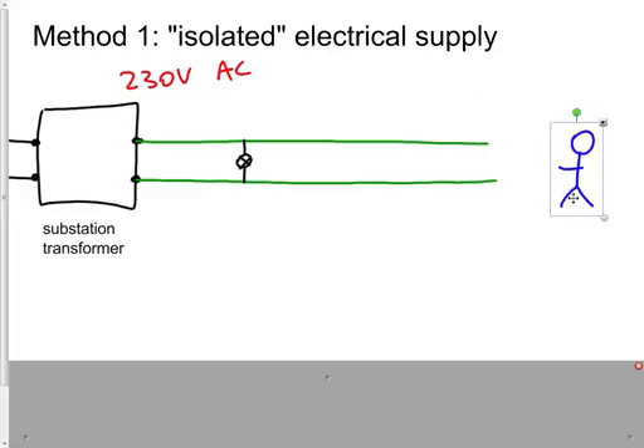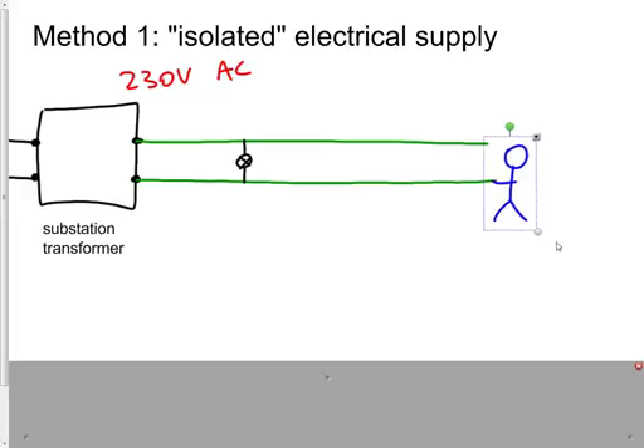But the interesting thing about this is that nothing is connected to the earth. So if you touch one wire and you are also connected to the earth because you're standing on it, that's totally fine in this isolated system. Because the substation transformer is not connected in any way to the ground, since all the wires are insulated, current can't flow through the ground back to the substation and form a complete circuit.